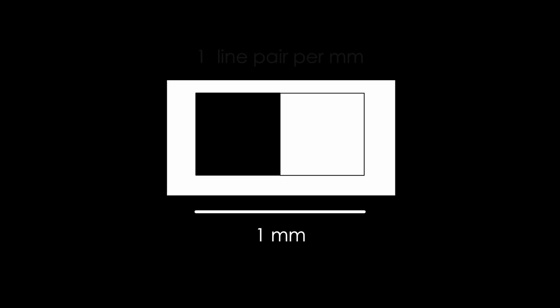In medical imaging, what we care about is useful resolution — how well can we delineate contrasted objects from one another? The way we do this is by measuring the line pairs per distance, usually millimeters. As you can see here, we have a black and a white pair of pixels together measuring one millimeter across, and you can see them perfectly. This would be one line pair per millimeter.